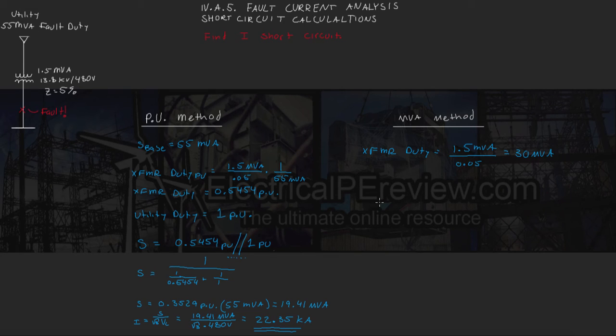And then next, we already know our utility duty is going to be equal to 55 MVA. And again, since these two are in series, we're actually going to add them together using the same method of adding resistance in parallel, which is the reciprocal of the reciprocal sums.